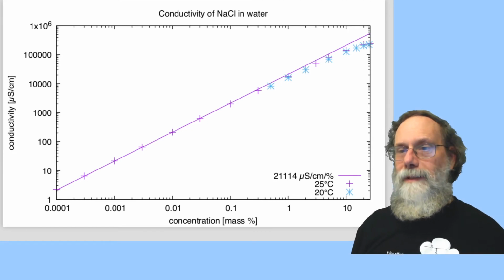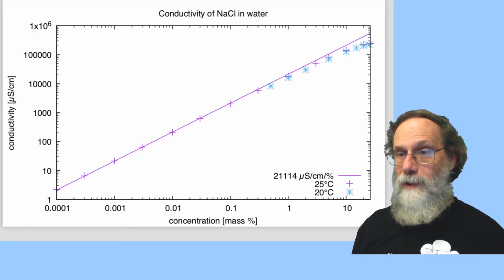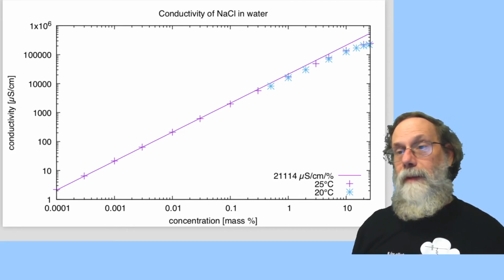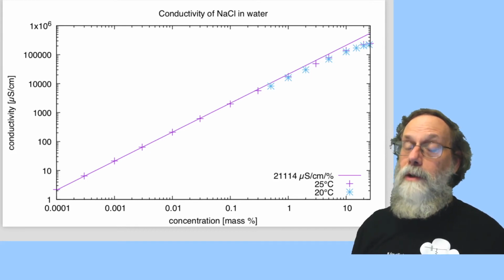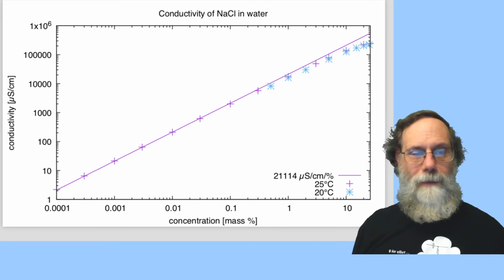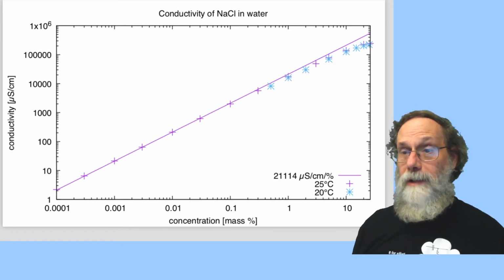And so the slurry that you have of whole blood, where you've got a lot of blood cells mixed in with the serum, reduces the conductivity of the serum. And that actually can be used for measuring the concentration of blood cells very rapidly, just by measuring the conductivity of the whole blood.